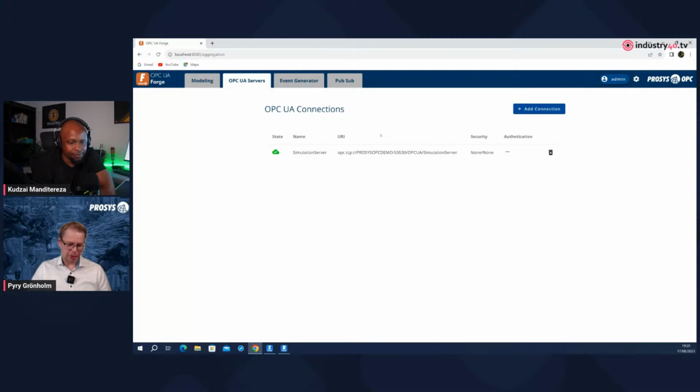And then there is the global discovery server, which is not really global, but would mean that you can find all the servers in a specific factory or network or some restricted entity, and that would enable auto discovery of the whole factory.